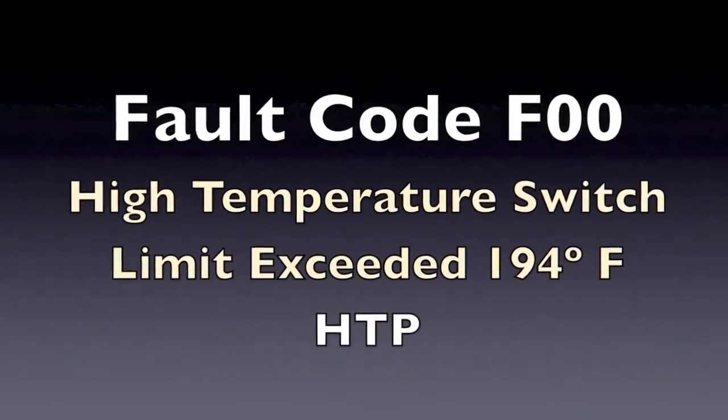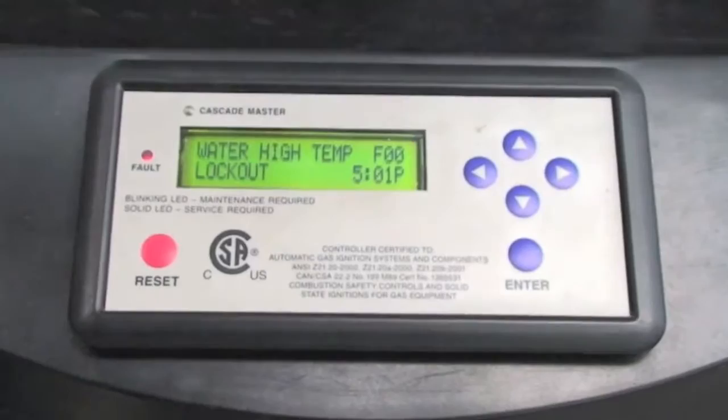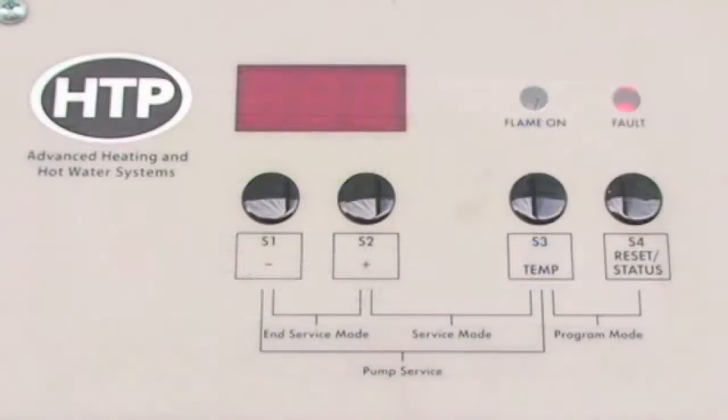If you are getting an F00 fault in your display, this fault occurs when the high-limit safety switch has been exceeded above the water heater's established safety limit of 194 degrees Fahrenheit.